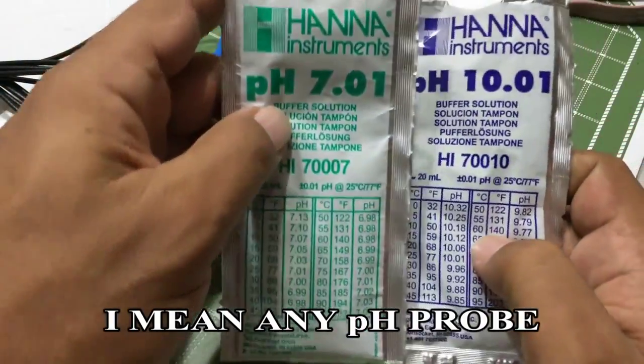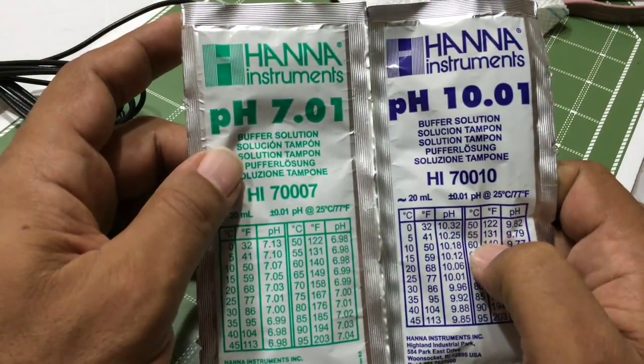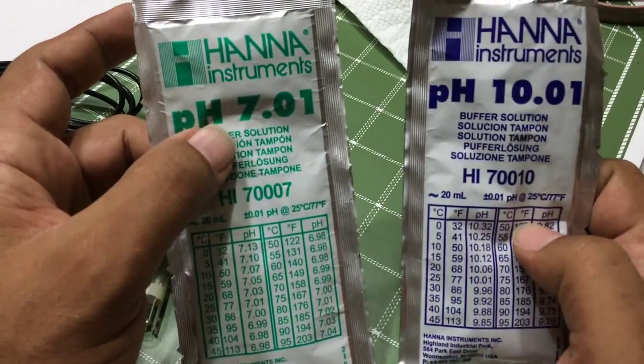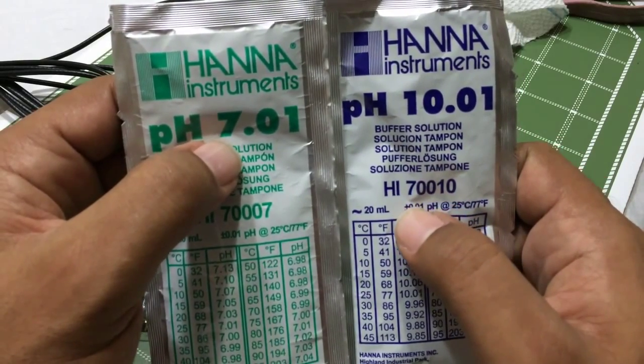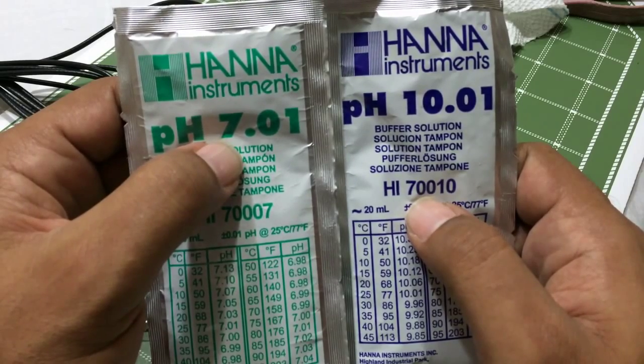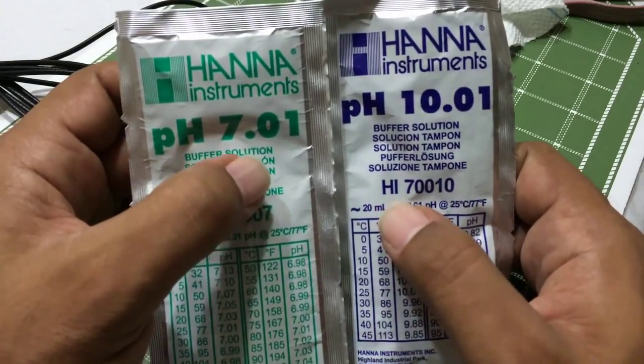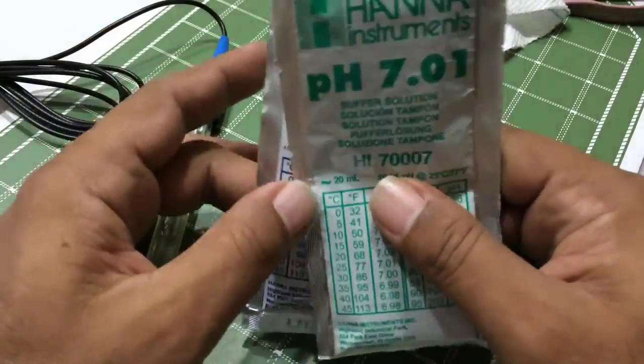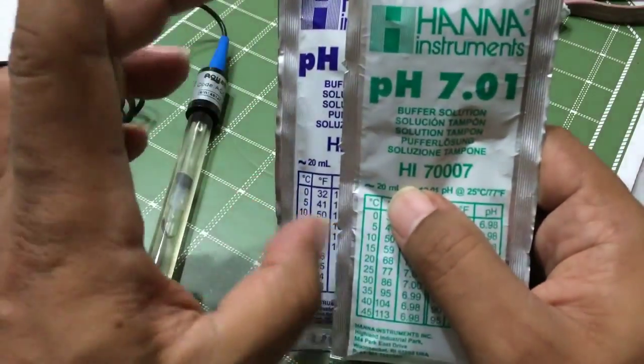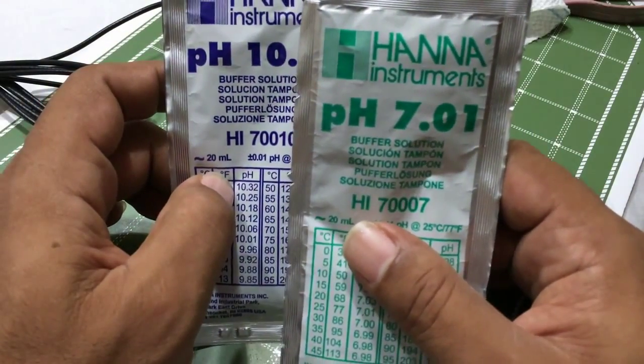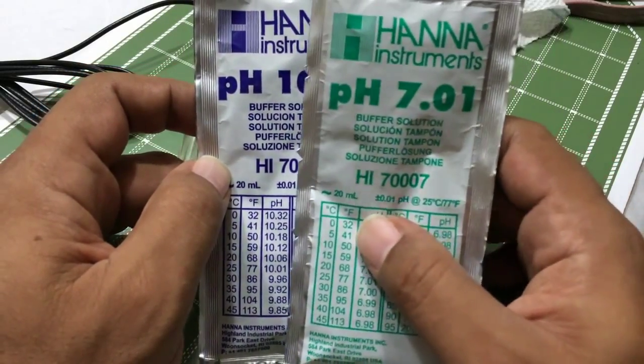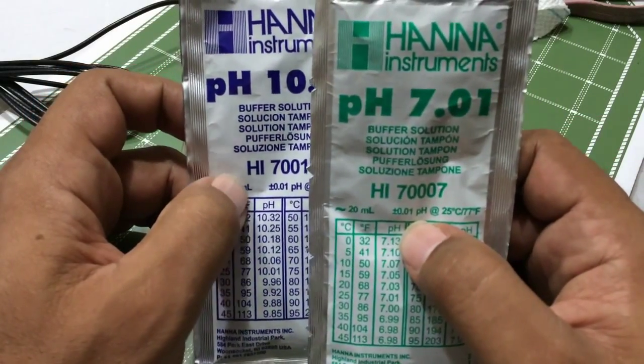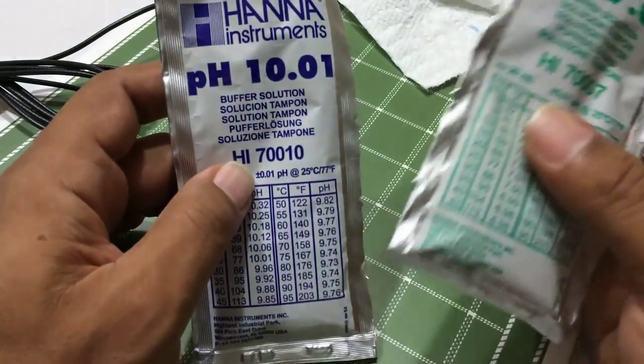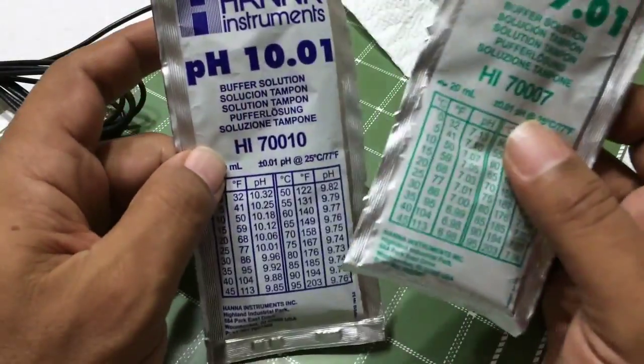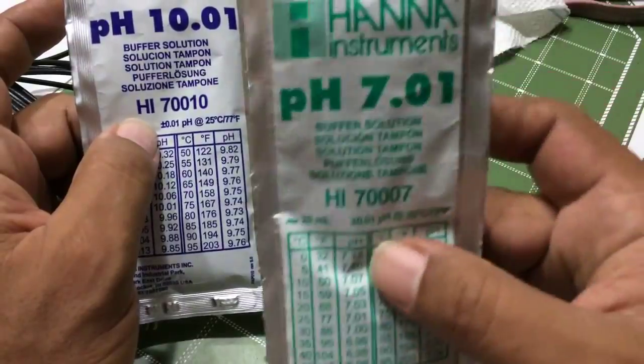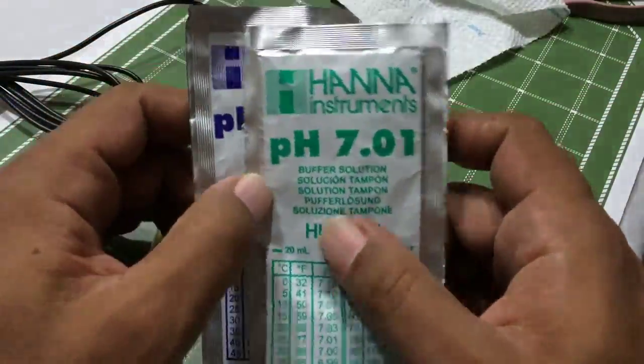For calibrating any probe, you typically need two standards, 7.01 and 10.01. Sometimes you'll see this as pH 4 and a 10. You basically want to pick samples that are closer in the range that you're going to be measuring. It'll probably give you more accuracy having two samples closer to what you're going to be measuring. I prefer the packets rather than buying a large bottle, because the pH will change over time, and if you don't use it within a specific amount of time, the accuracy of what's in the pouch deteriorates, or your larger bottle will deteriorate. So the packets basically stay fresh longer. You can buy these in packs of like 10 of each that come in a box, and that's just my preference on doing it.